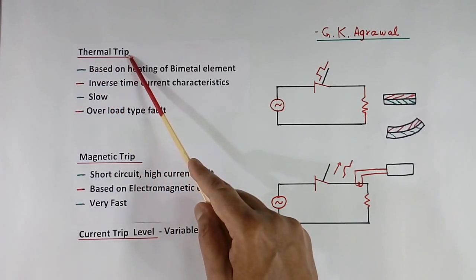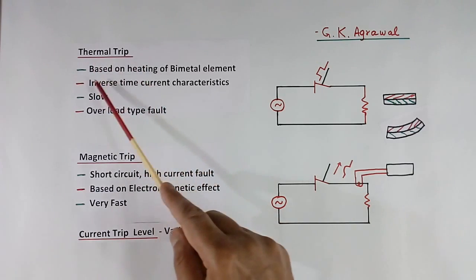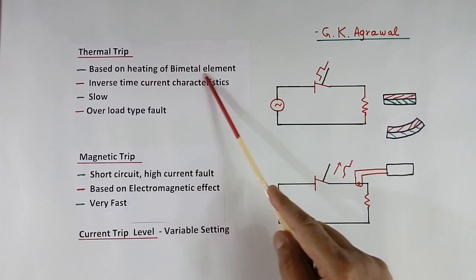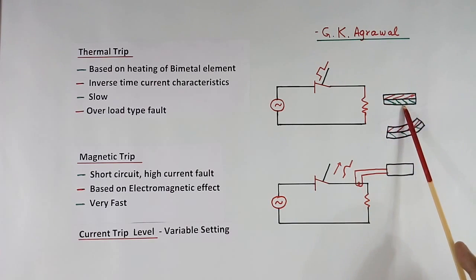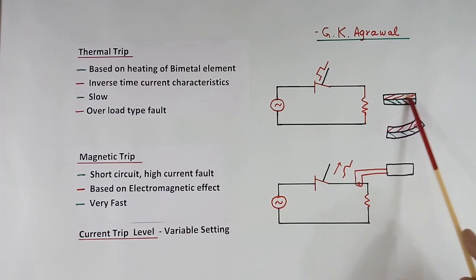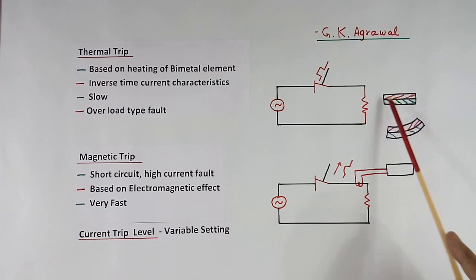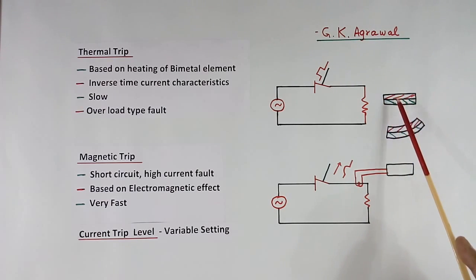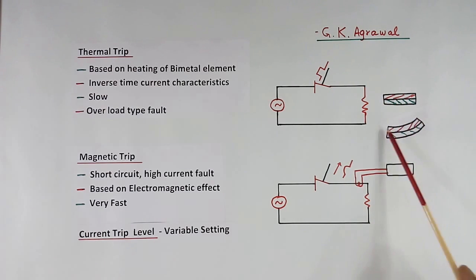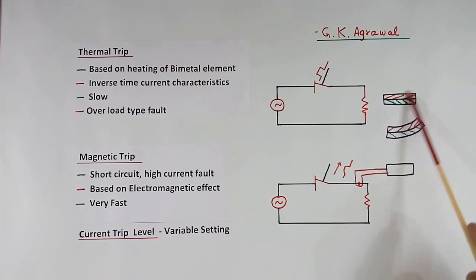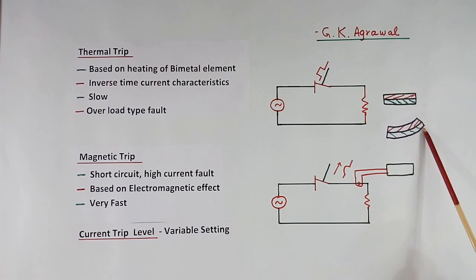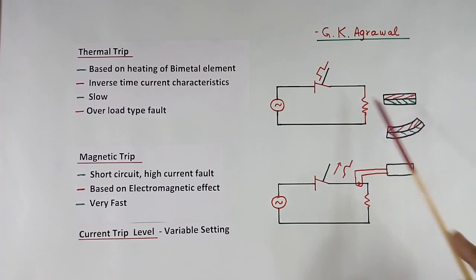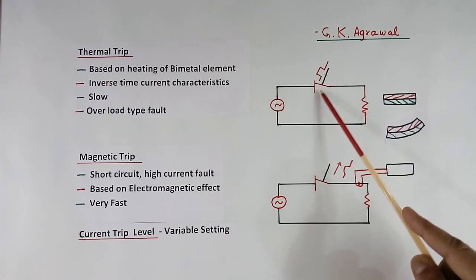Now, what is thermal trip? The thermal trip system is based on heating of a bimetal element. MCCB has one bimetal element. It has 2 types of metal. When it gets heated up, one metal will expand more than the other, so this strip will bend. This portion will move, and because of this movement, there is a mechanical arrangement which makes this contact open or trip.